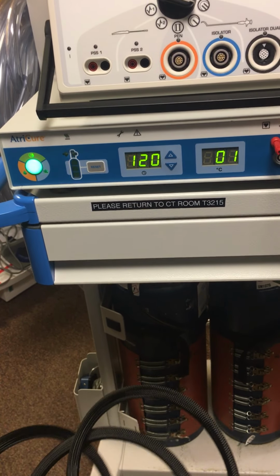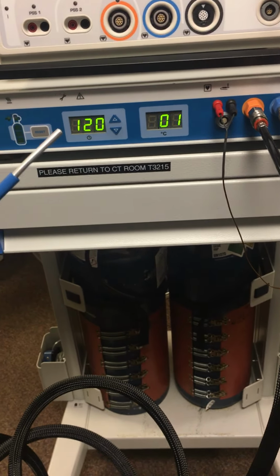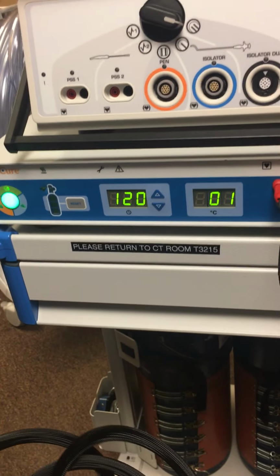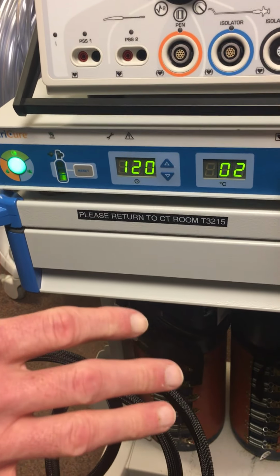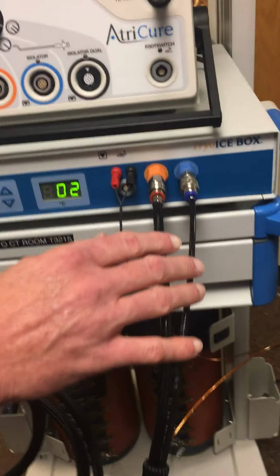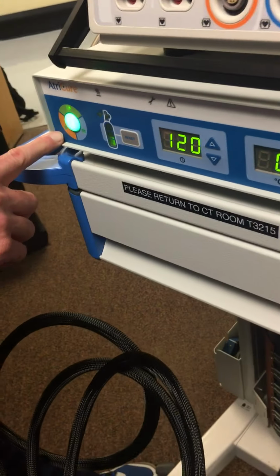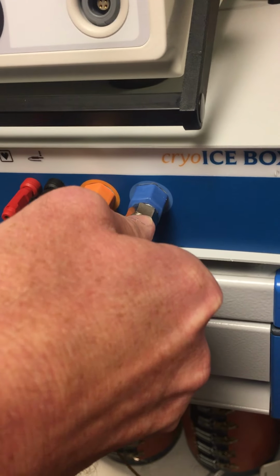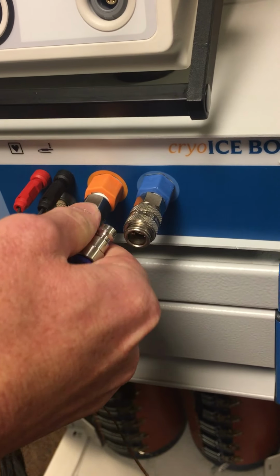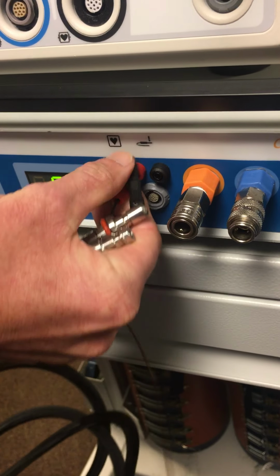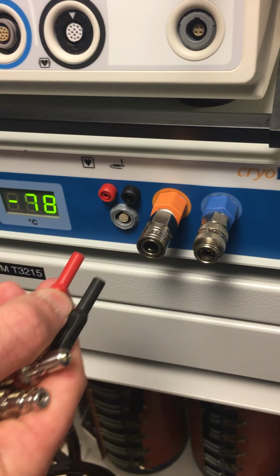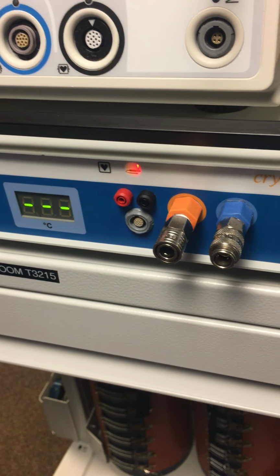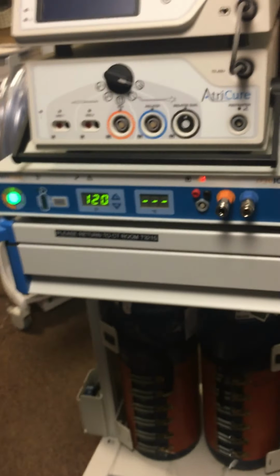At this point, we're going to go ahead and shut down the machine, okay? To disconnect the cryo probe, we want the light to be green, and then we're going to go ahead and just disconnect. Again, pushing forward on the quick couple on both of these, and then you're just pulling out the temperature probes. We have safely disconnected the cryo probe. Now we want to shut down the machine.